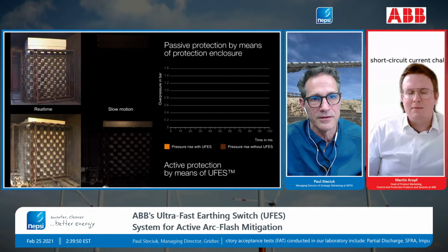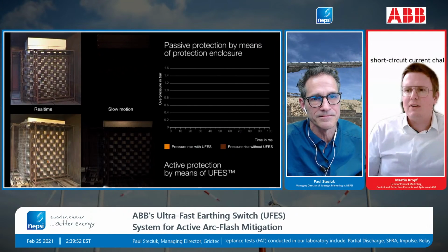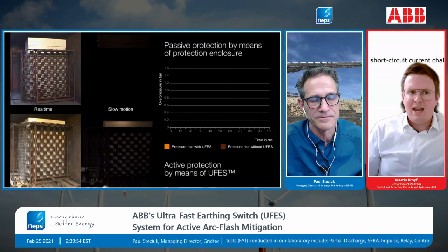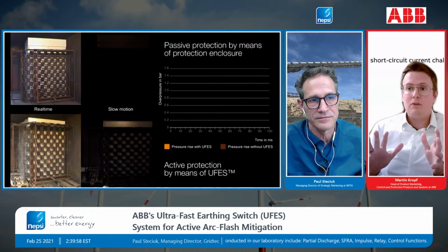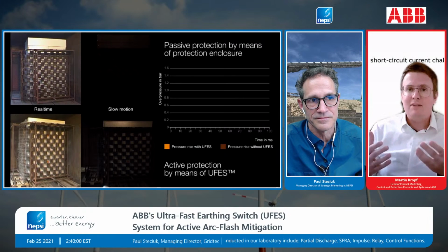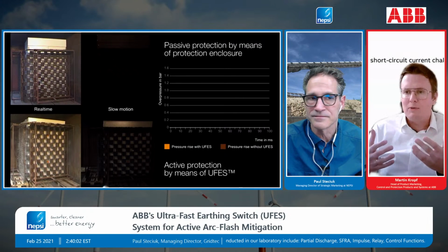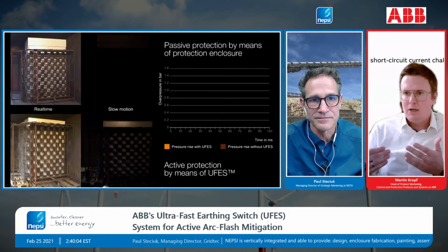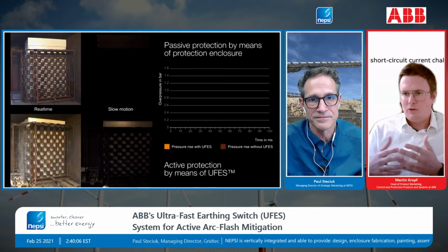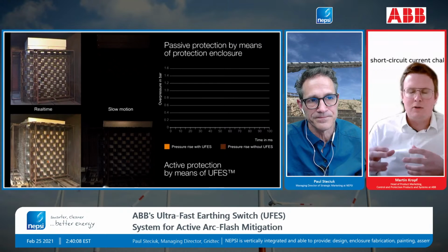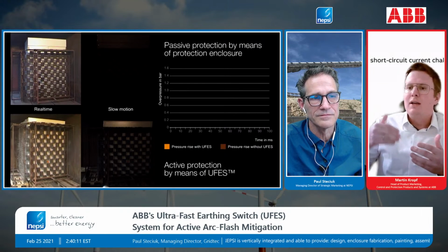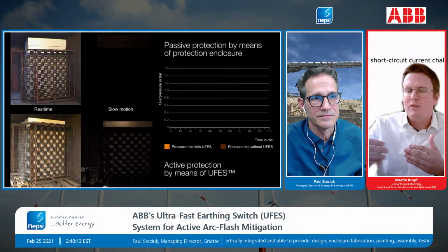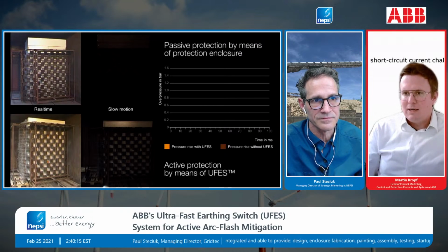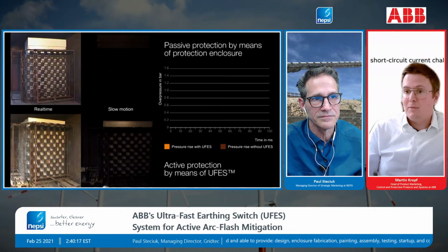We have these cotton indicators around it, from the side and from the front, so everything is closed, and the idea is to test the enclosure. If you test for a certain amount of time and none of these indicators catch fire, you are safe for this amount of time—the enclosure can handle this amount of current for this amount of time.